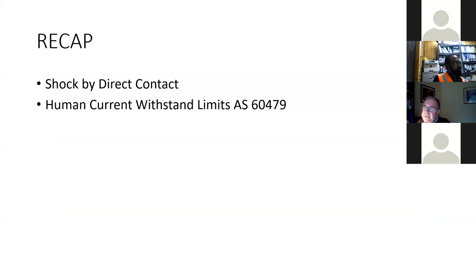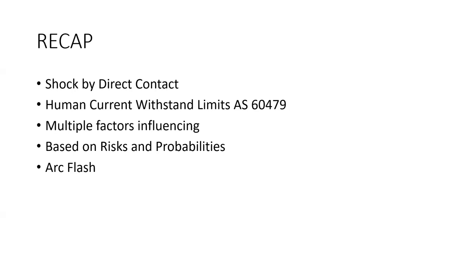So just recapping on last month, we talked about AS 60479 and shock by direct contact. So 60479 looks at the ability of the body to withstand certain currents and the probabilities of ventricular fibrillation for different situations. And there were many factors that influenced the situation. But it was a probabilistic approach. The factors were things such as wet or dry conditions, the voltage and the frequency, the body current path. And we even looked at the time of contact with respect to the heart cycle.